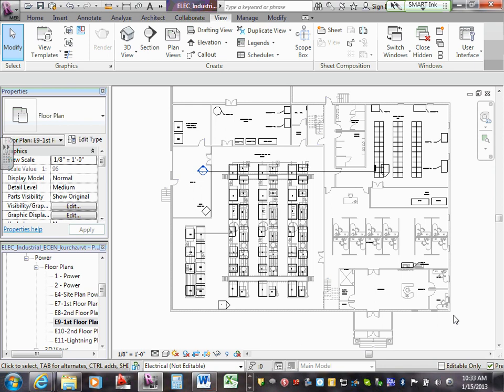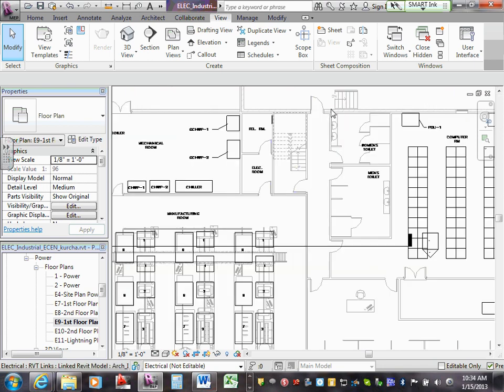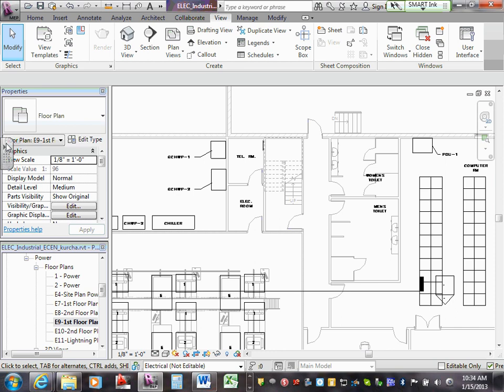In corridors, notification devices, you have to have a horn strobe within 15 feet of each exit. And horn strobes can be 100 feet in between the next device on a corridor that's less than 15 feet wide. In a corridor, if it's less than 15 feet wide, you can go 100 feet between devices.